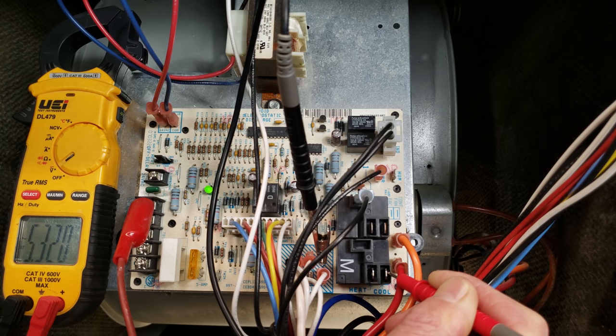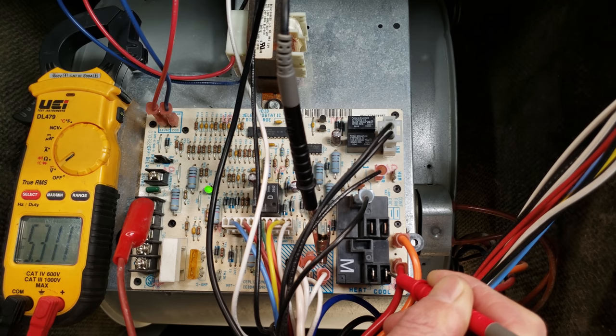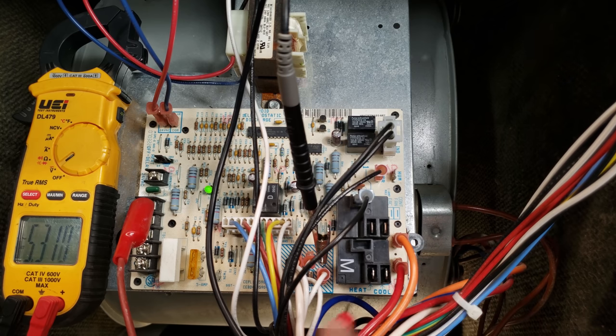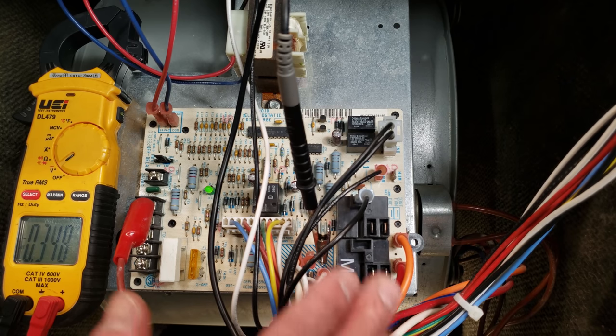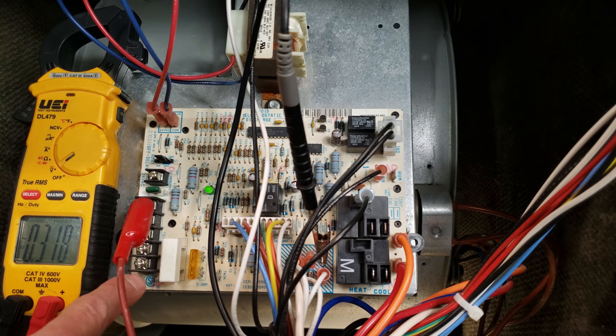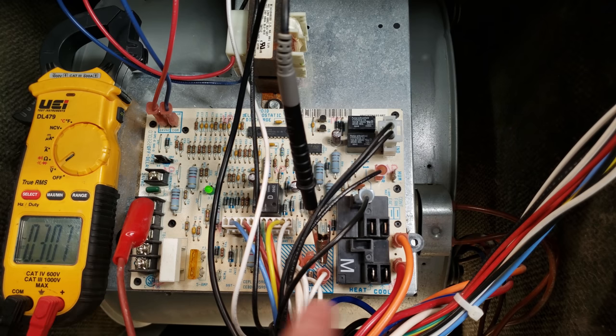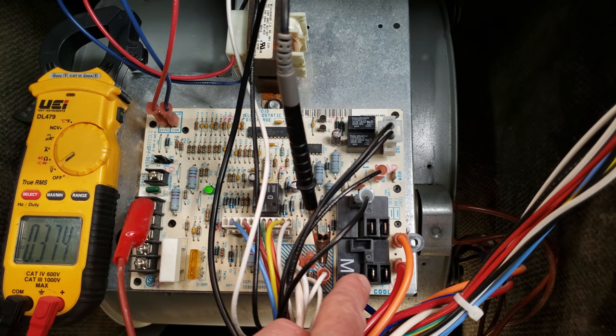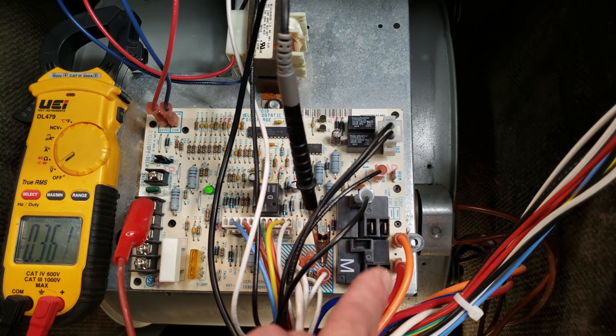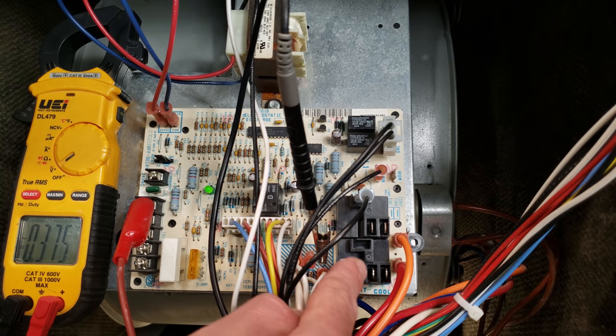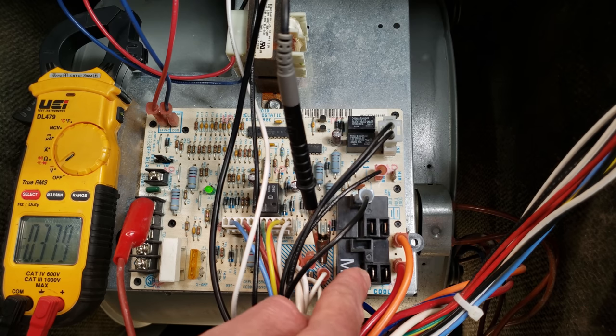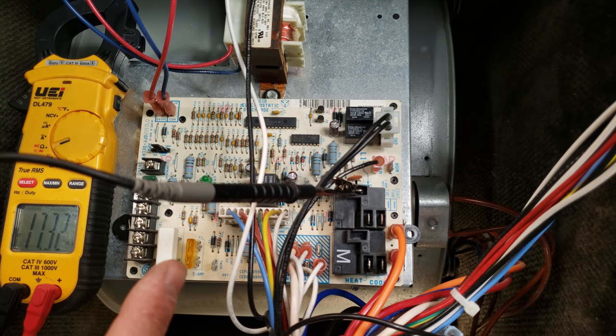Now you see that we no longer have power to the blower motor, we only have five volts right there. That's for air conditioning mode. But anytime you turn your fan on by putting 24 volts in the G terminal it may take one or two seconds for the blower motor to turn on and then it may be one or two seconds for the blower motor to shut off.